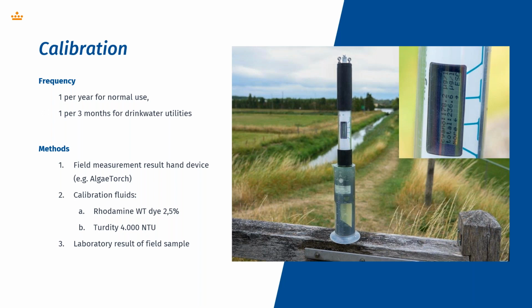The second method is to calibrate with fluids. The blue algae and the green algae sensors are calibrated with rhodamine WT dye 2.5%, where you can make a dilution series to measure. The turbidity calibration fluid is 4,000 NTU, which you can also dilute to set up a calibration. The last method is a laboratory result of a field sample, which you can also enter into the web portal and connect the RFU result to your laboratory result.